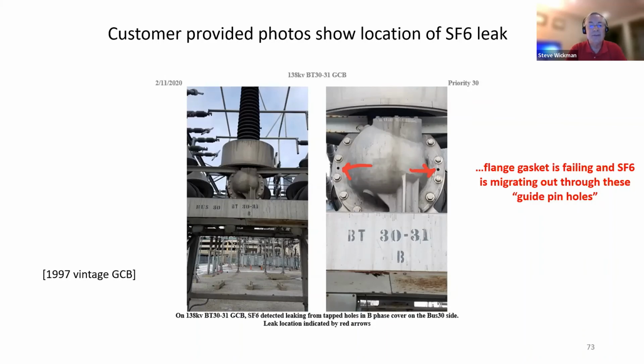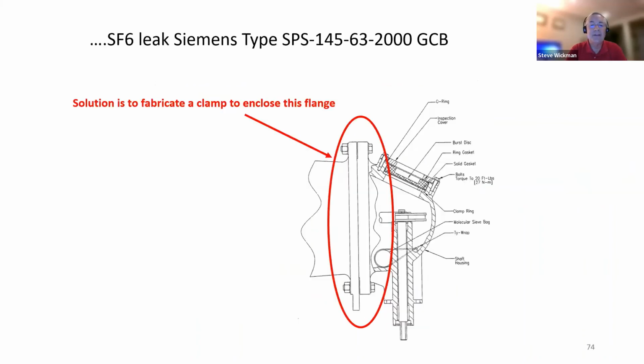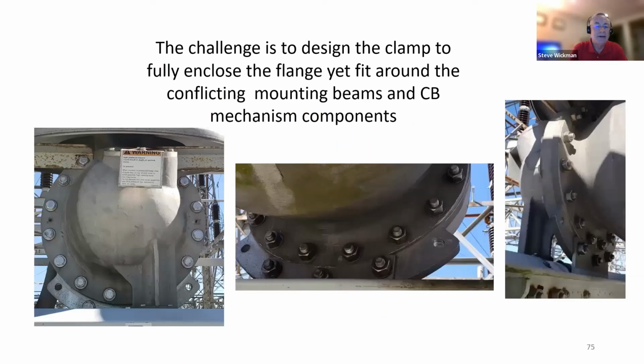Well, then you do that, it's going to migrate around the rest of that flange. So this is the flange that we needed to tackle to enclose around. Some crazy interferences to do that, because not only is it the flange that holds that end of that breaker together, but it also supports the pole to the structure that it sits on.